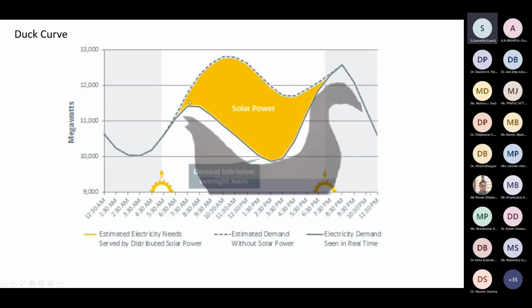If there's a gap, for example 1000 megawatt, and I'm producing 1000 megawatt by solar, that gap can only be fulfilled by solar. That means I have to shut down my steam turbine or gas turbine during that period, because you cannot pump excess energy into the grid, otherwise the grid will fail. So at peak solar time, you have to shut down your coal-based power plant.